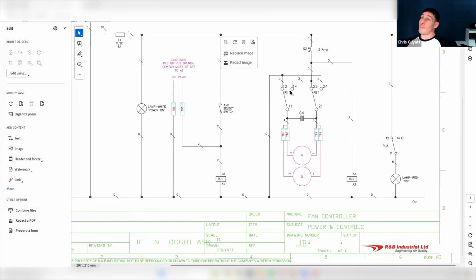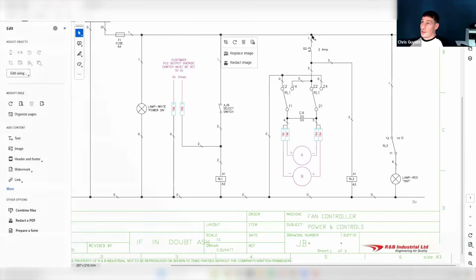But on this other side of the relay, you can see that it just stops at 14 because this contact isn't switched over this side because it's just in its normal state. So basically we've got 24 volts going down one side, but it's not going down the other side. So what happens in terms of the power is, let's just follow it from the top again. Providing this isn't tripped out, we've got 24 volts going down here, and then we've got 2 dampers.